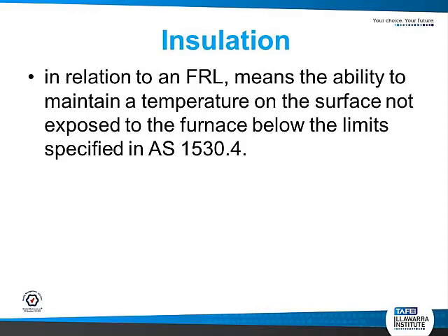Insulation means the ability to maintain a temperature on the surface not exposed to the furnace below the limits specified in the same Australian Standard. So that means that obviously it's not getting too hot on those walls while you're trying to get through.